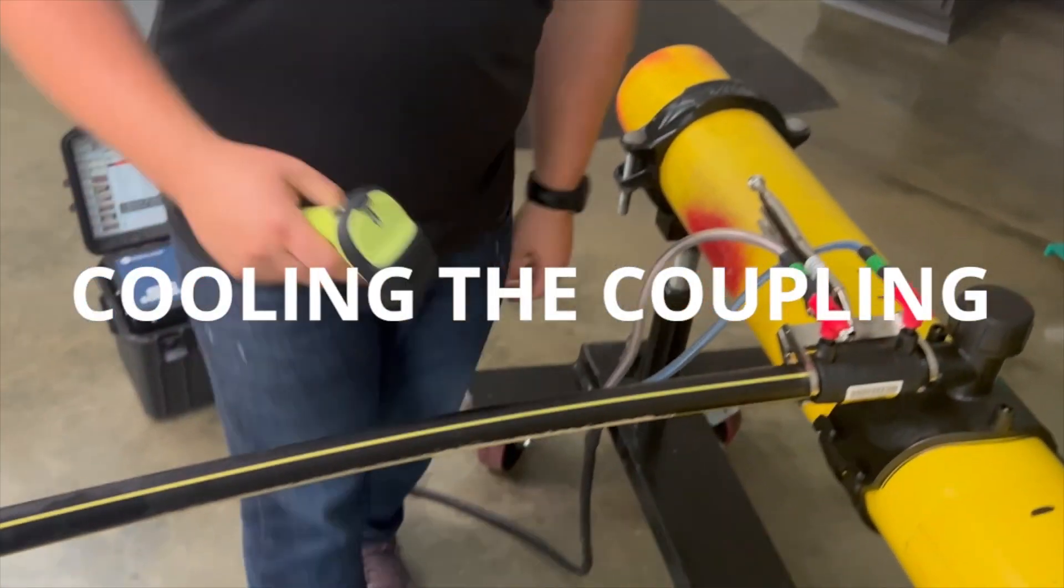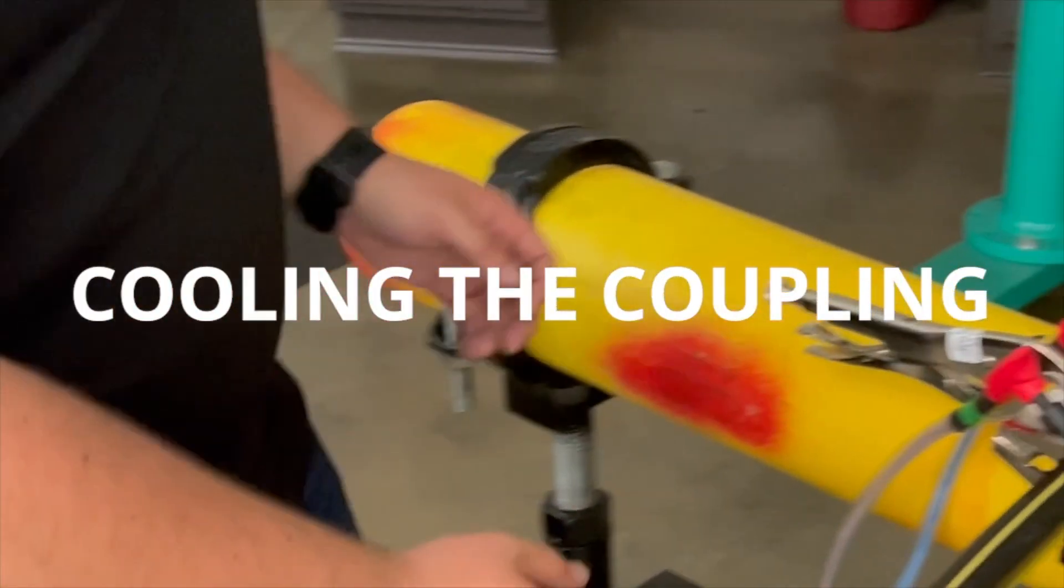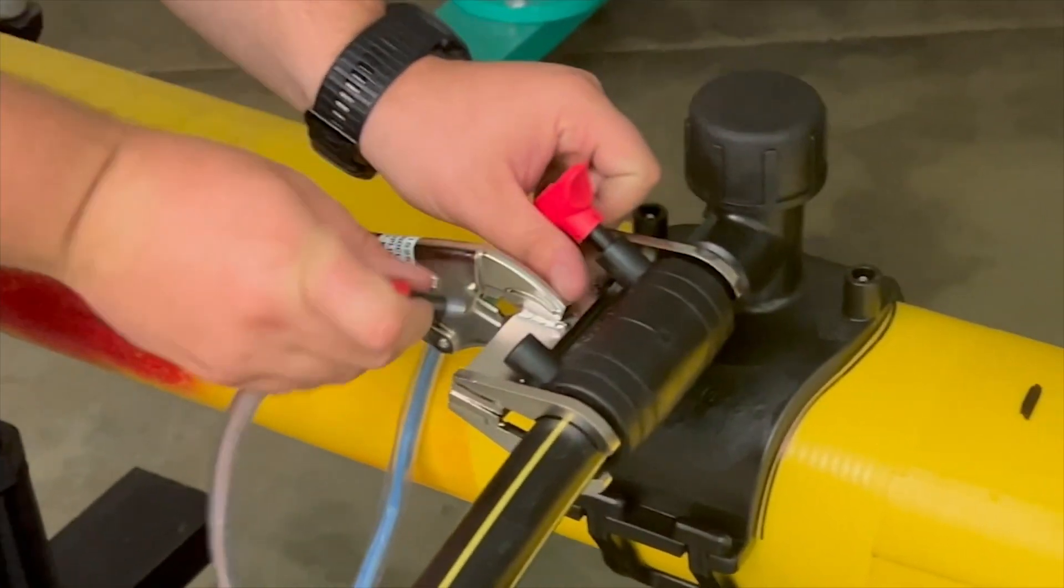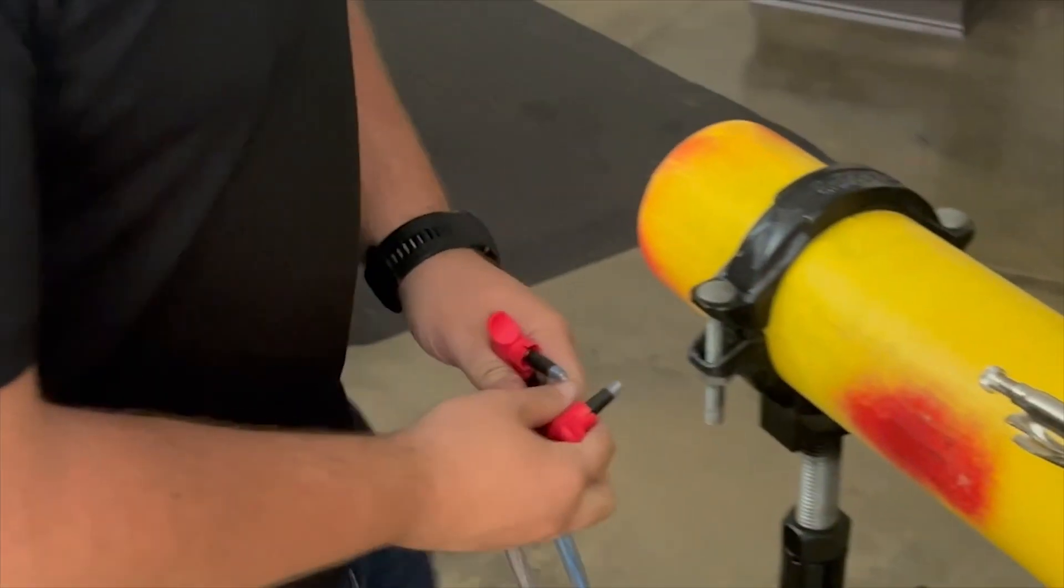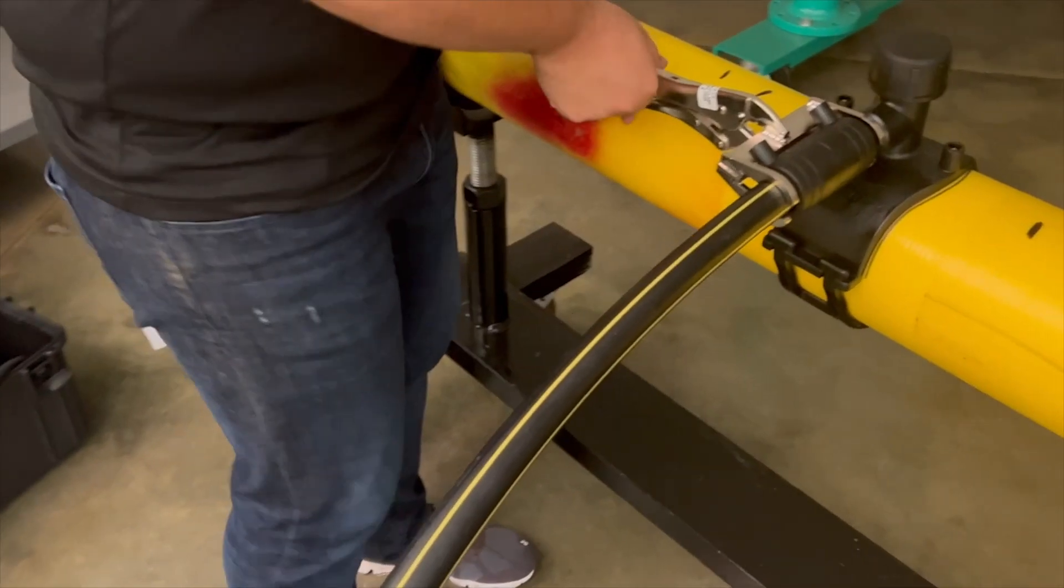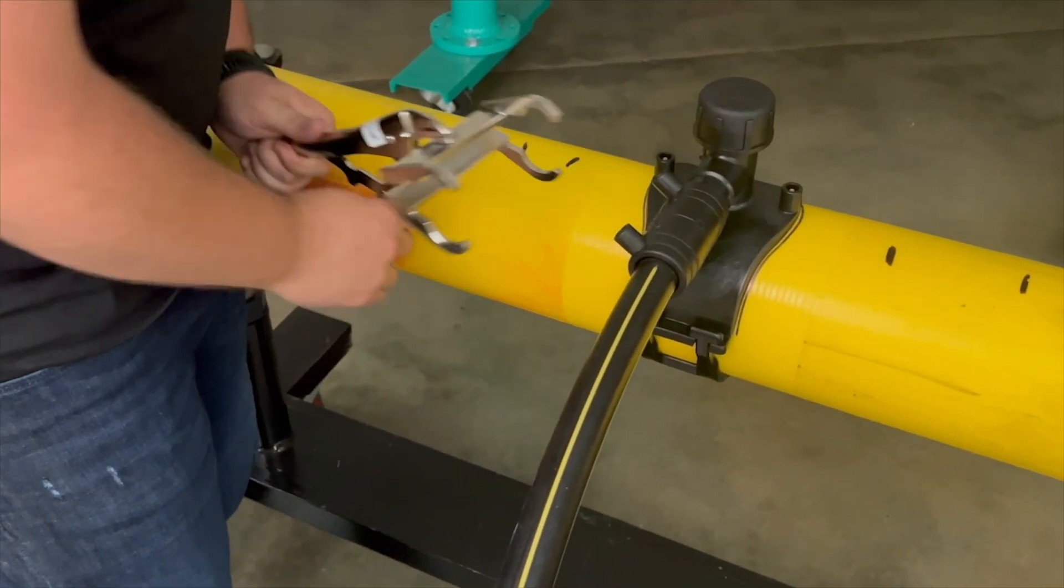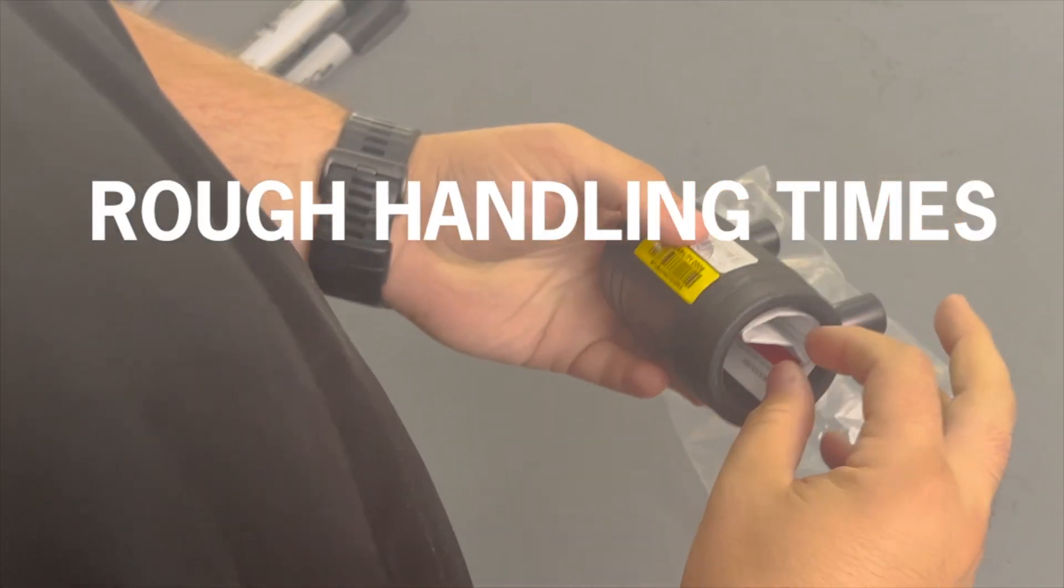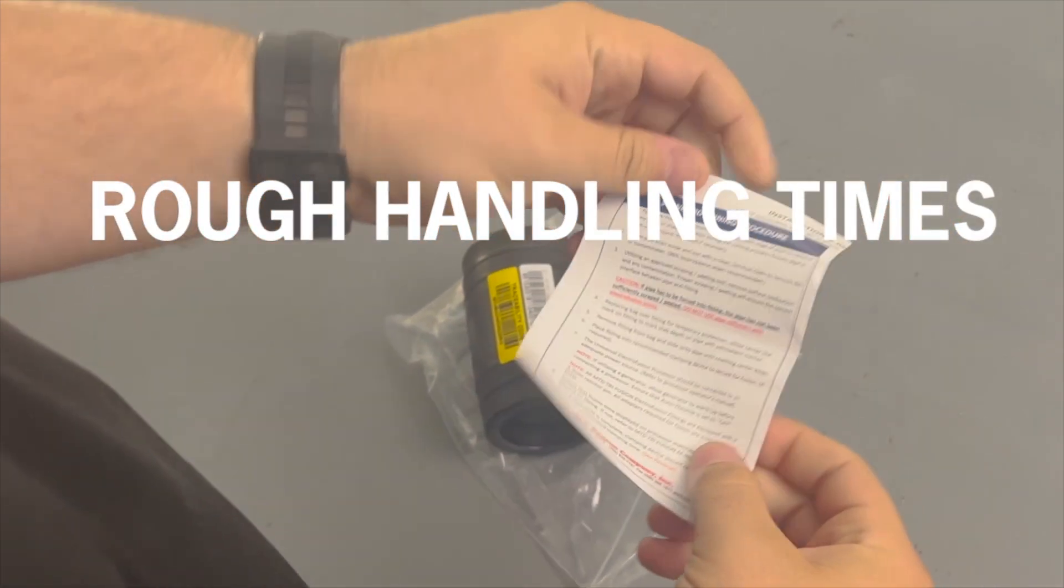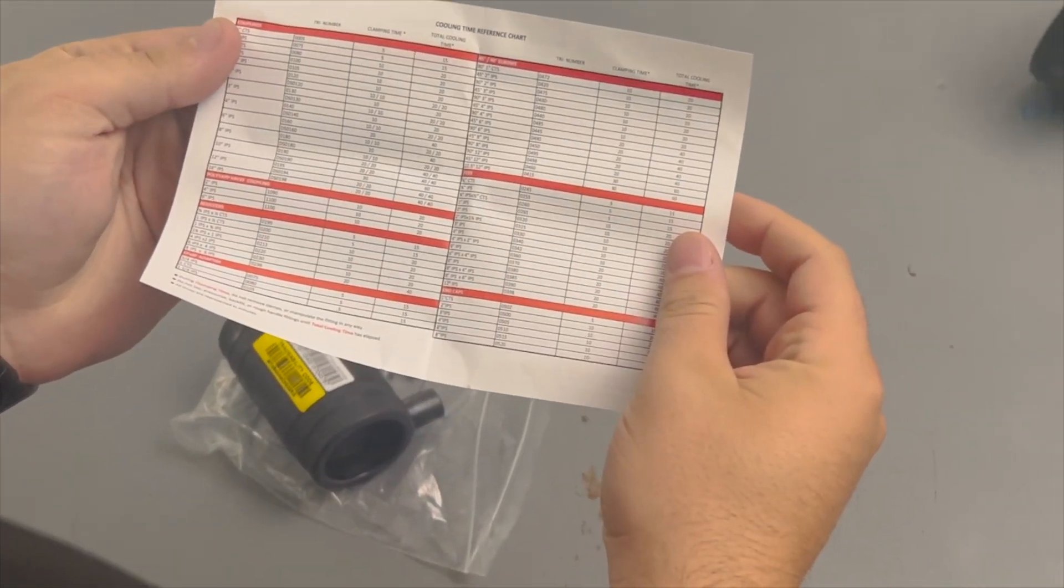Part 7: Cooling the coupling. Since we're using an external clamp on this joint, make sure that clamping time has elapsed before removing the clamp. Clamping time is printed on the coupling body, coupling labels, and is displayed on the processor. Prior to proceeding to the next step, make sure rough handling times have elapsed. For published rough handling times, refer to the printed insert included in the coupling package. If this is not available, simply double the time printed on the fitting label.